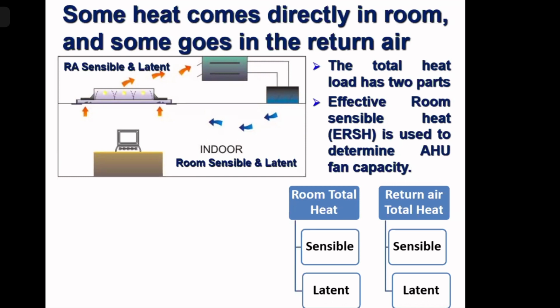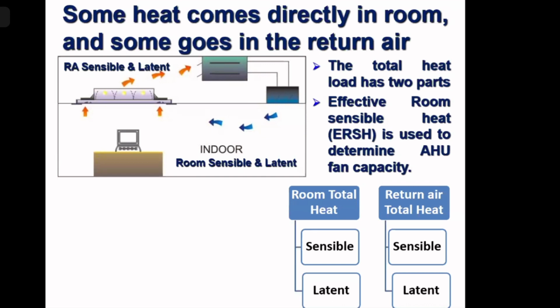And cooling coil sizing, how much cooling has to be done, dictates the size of my chiller. Chiller has to supply that much of cooling. Otherwise, cooling coil itself can't cool. It's only a support service. It provides a support service. But basically, cooling is done by chiller. So my chiller sizing depends on my room total heat plus return air total heat.